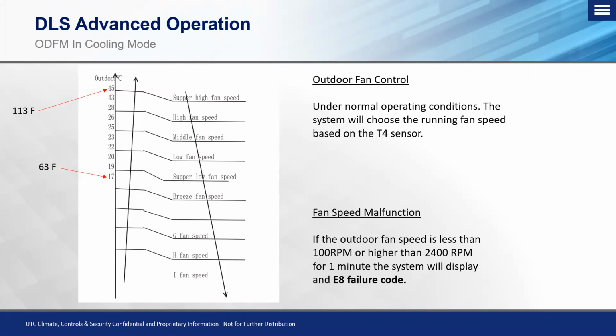So if we have a situation where that sensor is reading improperly, we could run into a situation where we might go off on high head pressure or a P1 code. But typically that's not what we run into. It's very rare that we see that. I have very few sensors that I have confirmed with technicians in the field that have failed. Typically, there are other application-based underlying reasons why a P1 code would happen, which would be a high pressure protection. But as a basic rule of thumb, this is what we're looking at for T4 sensing conditions to initiate different fan speeds. And essentially, it acts like a motor master. It's controlling head pressure.